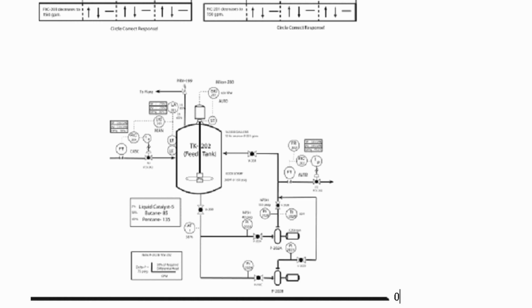On the other side, there's a drum connected with electrical signals, the SIC, which is a speed indicator controller, which is actually telling the tank to spin at 650 RPM. And then the SIC will go to the ST, which is a speed transmitter, and that transmitter will tell the feed tank to spin at 650 RPMs.